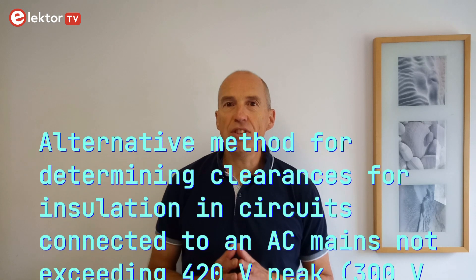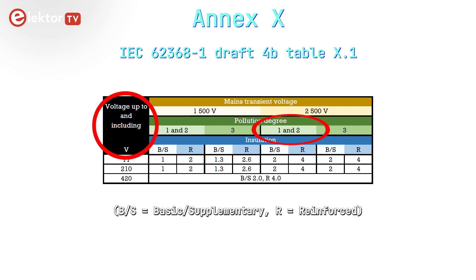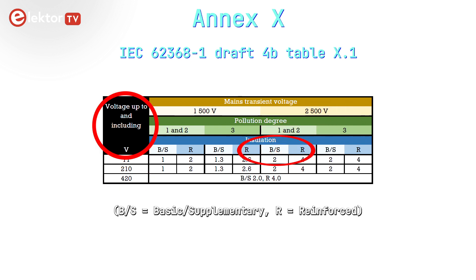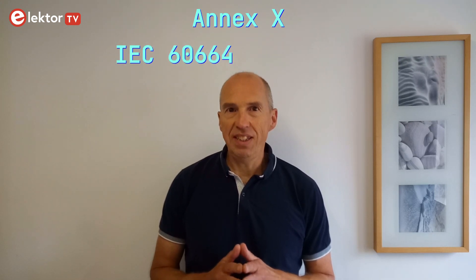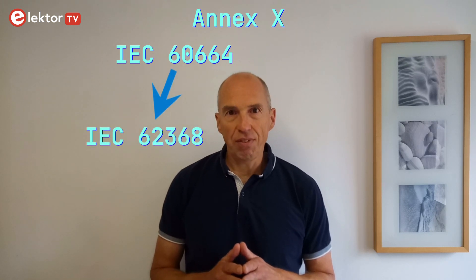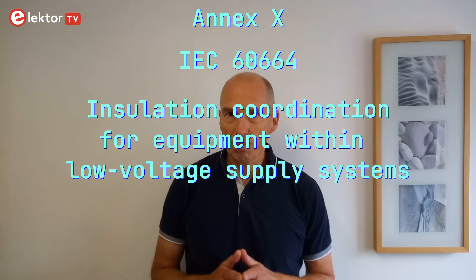There is also an Annex X, which provides an alternative method for determining clearances for insulation in circuits connected to an AC mains not exceeding 420 volts peak or 300 volts RMS. All things equal, using the data from this Annex we find for reinforced insulation a clearance distance of 4 mm instead of 3.6 mm, and for functional or basic insulation 2 mm instead of 1.8 mm. It seems that Annex X allows equipment that already conforms to IEC 60664 to also conform to IEC 62368. Making the clearances the same as the creepage distances determined for my scenario, they also comply with Annex X, so I am probably good.